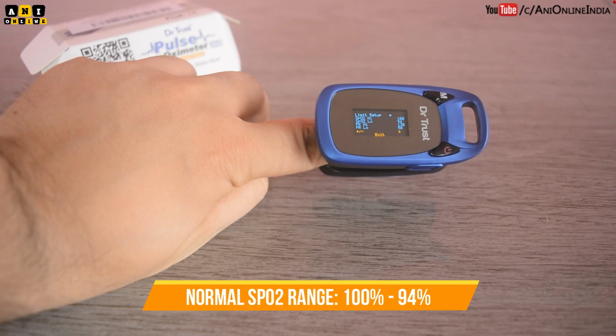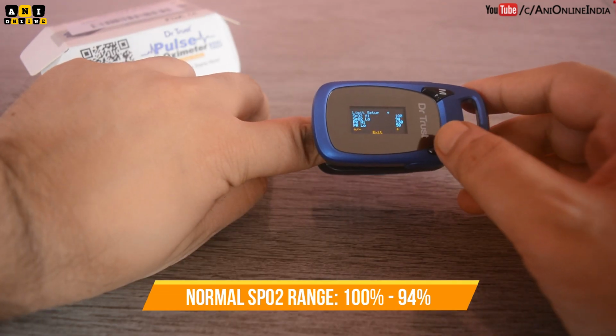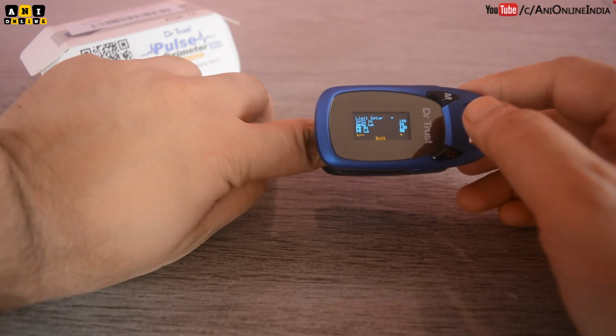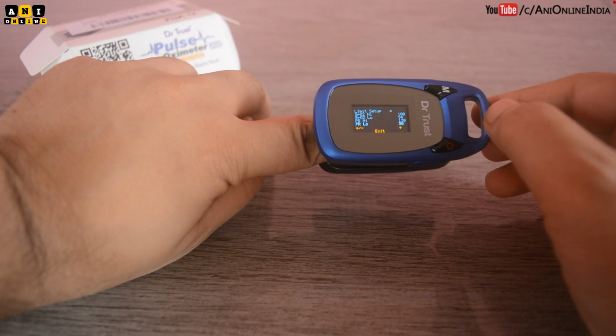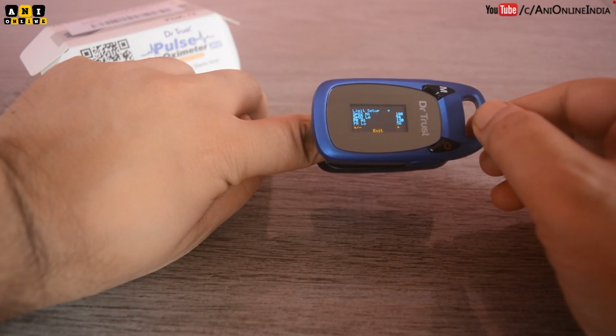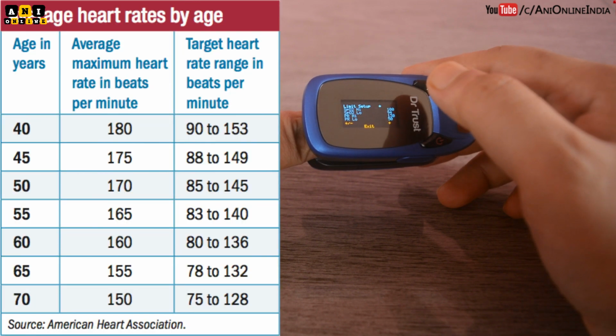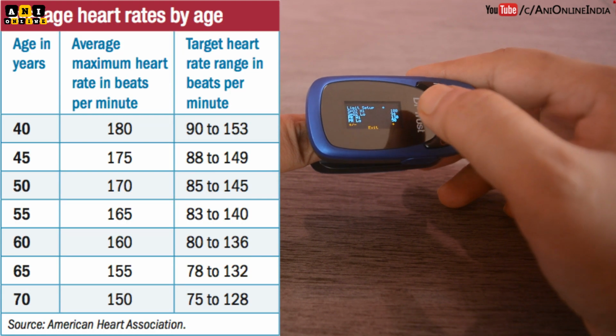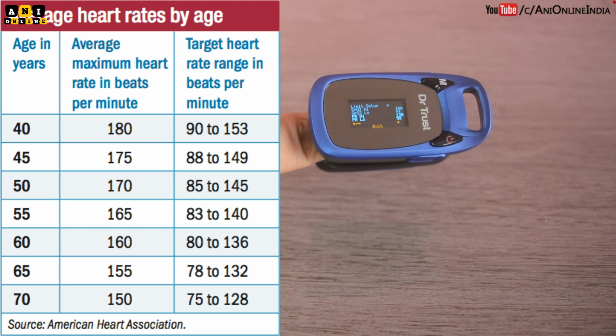So here you can see the limit setup. SpO2 high means 100%, so beyond 100% it can't go, and the lower limit is 94%. So if your SpO2 level goes out of this range, it will start beeping. The upper limit of the pulse rate is 130 and the lower limit is 50.